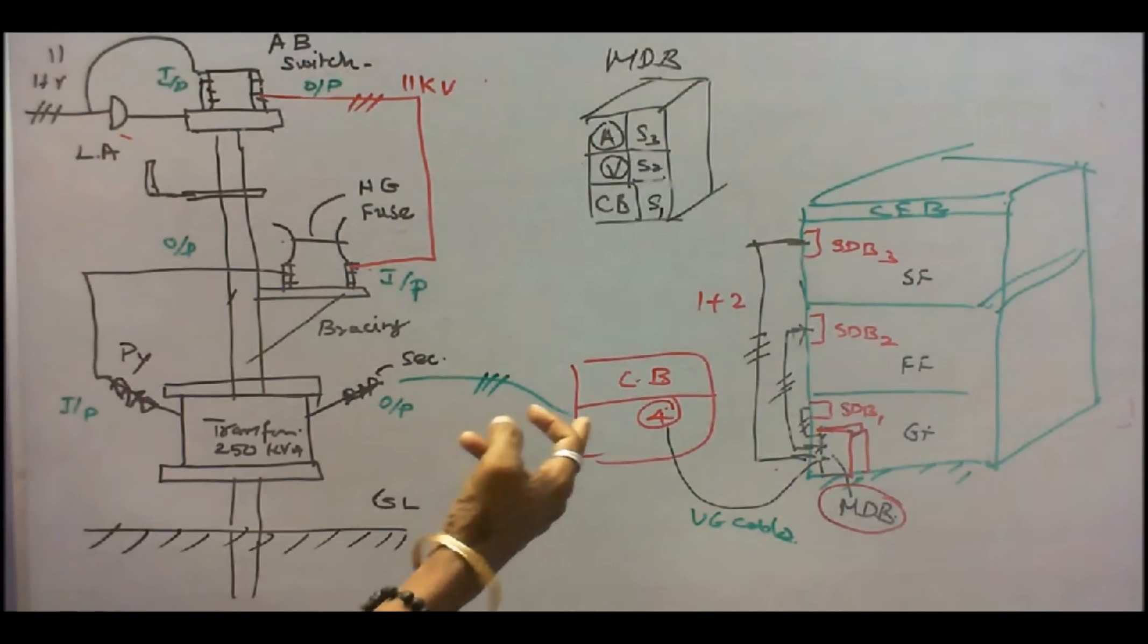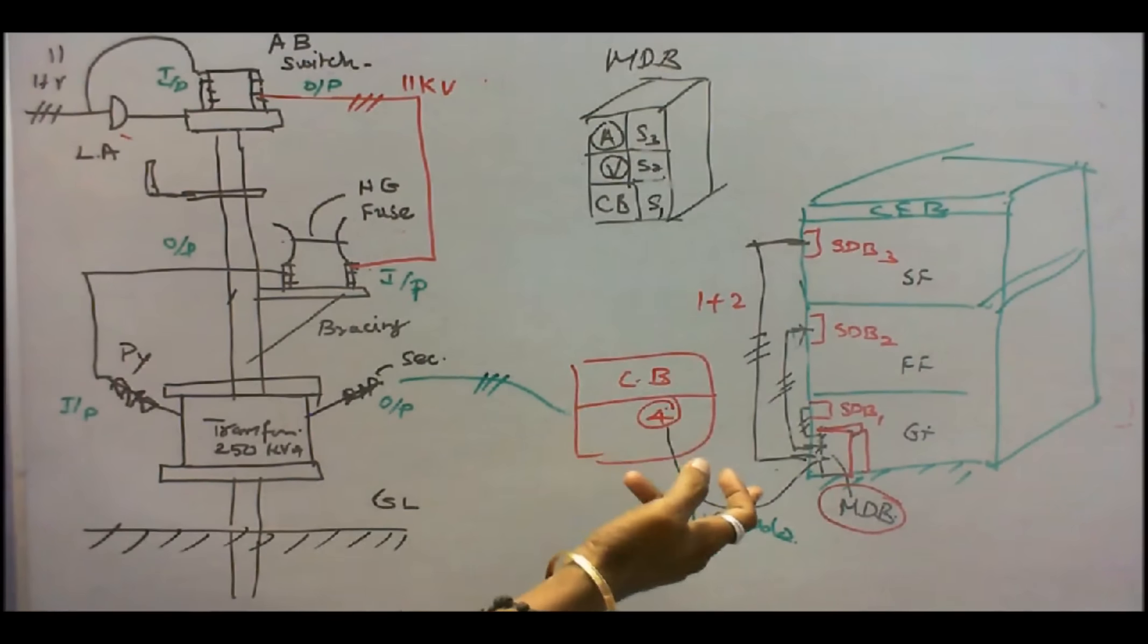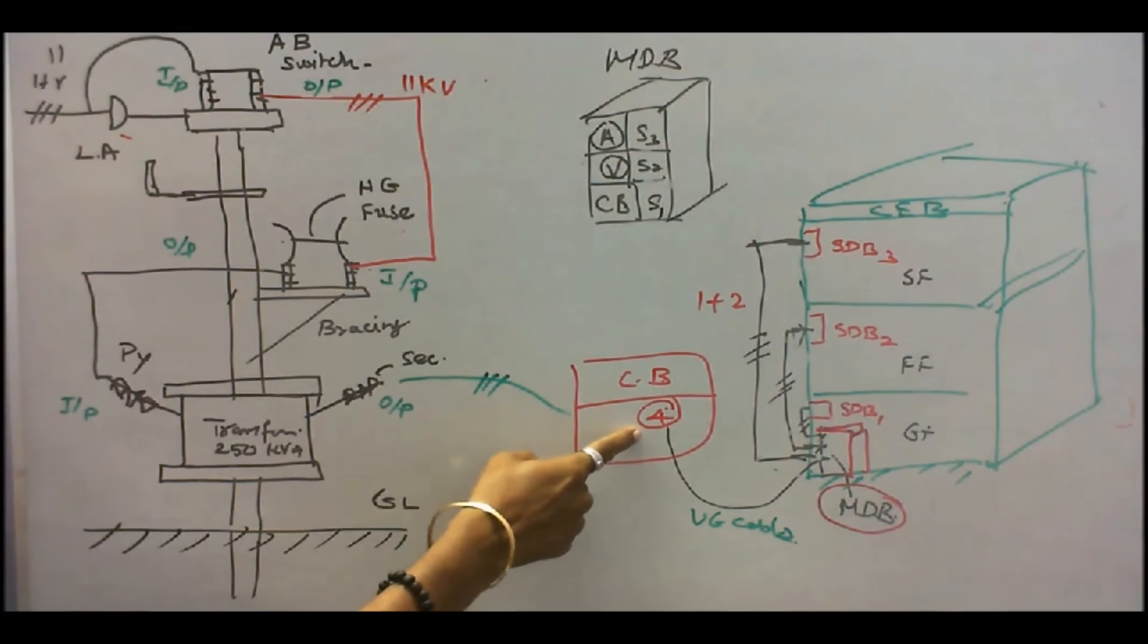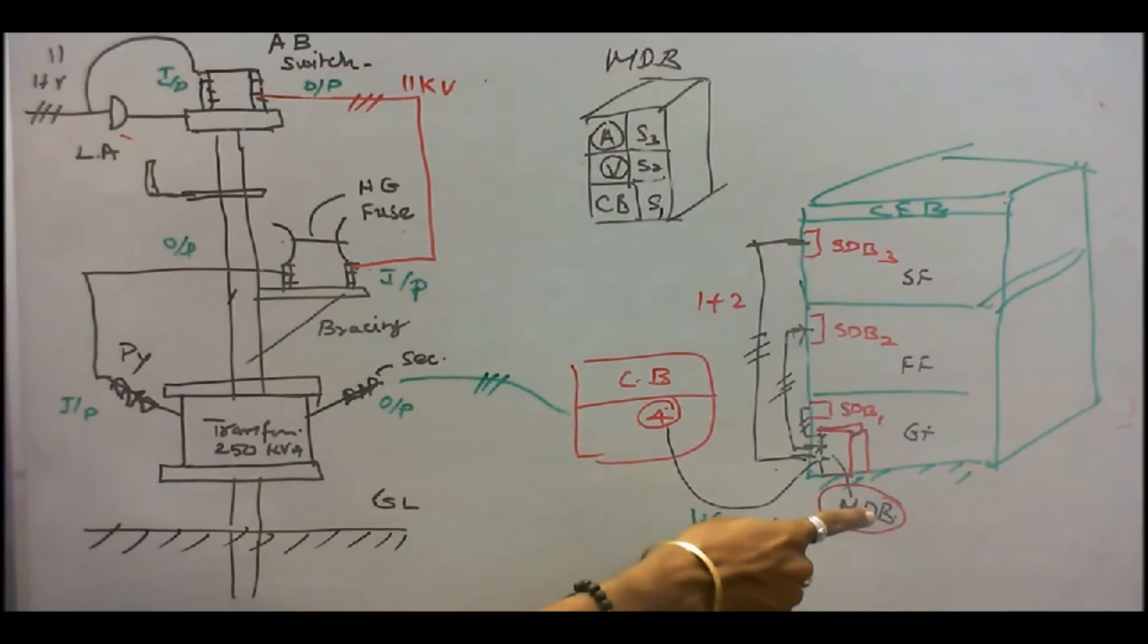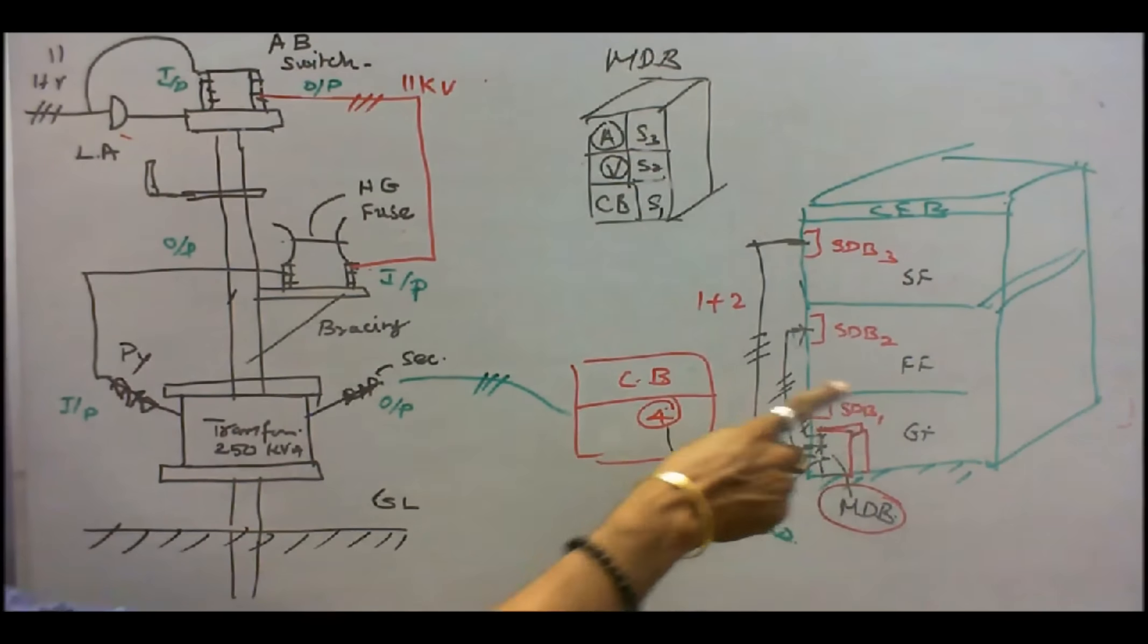Now we will see how distribution takes place in the civil engineering block. This is the main distribution control board. Switch 4 goes to civil engineering block. The civil engineering block is 1 plus 2. Ground floor, first floor, second floor. From switch 4, I am connecting to the MDB, that is main distribution board, through an underground cable.